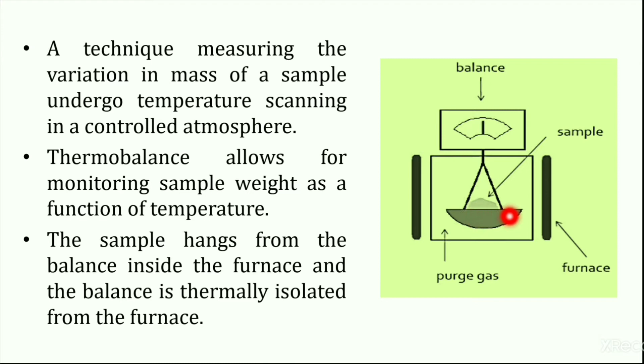Every thermogram denotes unique properties related to the physiochemical changes of the sample under investigation. For example, the first line spectrum denotes that the sample under analysis remains stable with no decomposition. Here, solid phase transformation, melting, etc. cannot be detected. In the second curve, the rapid initial mass loss denotes desorption or drying. If this characteristic is true, then the rerun of the sample should result in the type 1 curve.